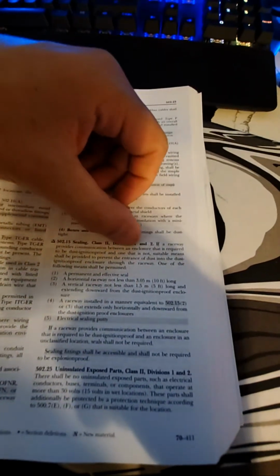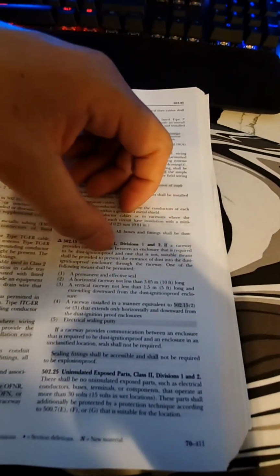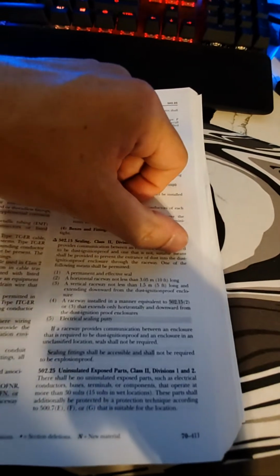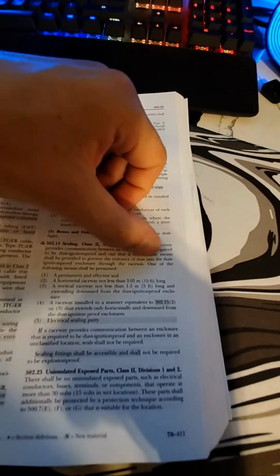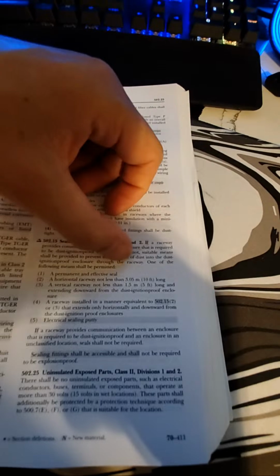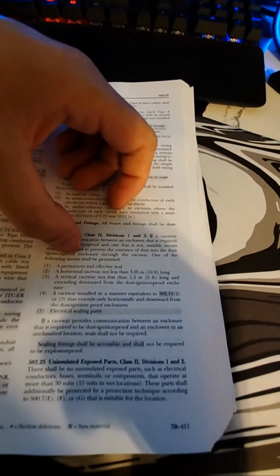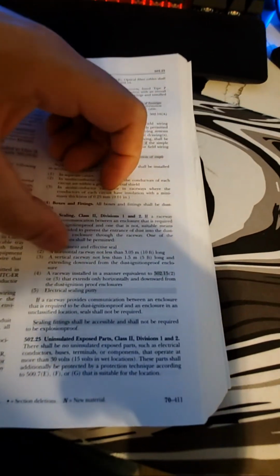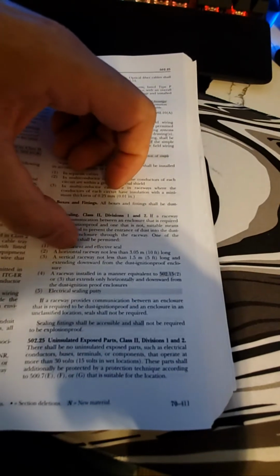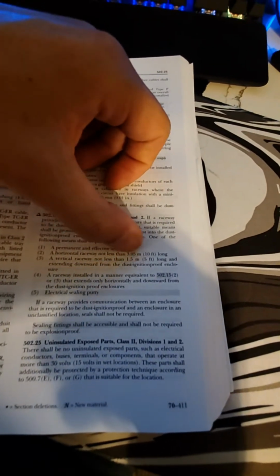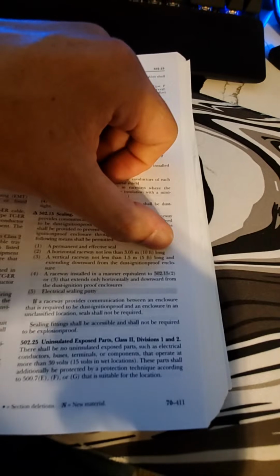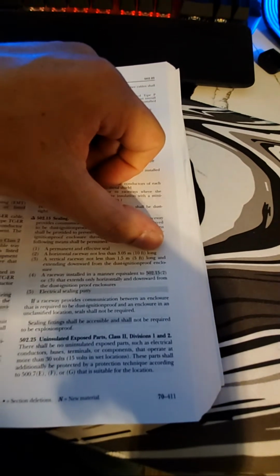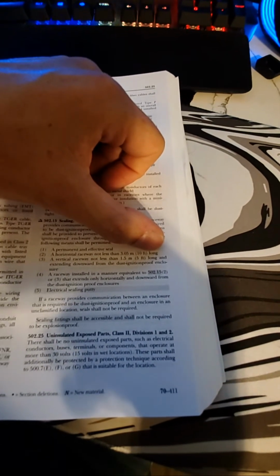So it says one of the following. If a raceway provides communication between the enclosure that's required to be dust ignition proof and one that's not, suitable means shall be provided to prevent the entrance of dust into the dust ignition proof enclosure through the raceway. One of them is required. We had a horizontal raceway not less than 10 feet long. So if it's 15 foot long, maybe we don't need anything.